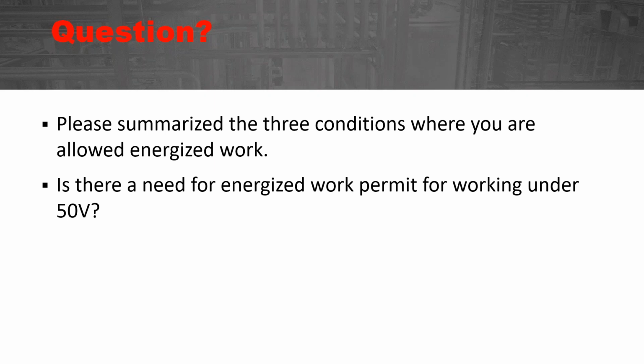Also, I think we've got a question coming up later about continuous process, such as steel making or glass making. I was teaching in a plant in Crossville, Tennessee, about an hour and a half from home, halfway between Nashville and Knoxville. They have an area they would consider continuous process, where ceramic tiles are going through a kiln that is hundreds of feet long, and if they just stop that midway, these tiles are going to burn up and it's going to cause a big problem. Now, all of this, the employer is going to have to demonstrate that working on this energized is permitted. And going back to 70E, if you're going to do work on energized circuits, unless it's less than 50 volts, then you're going to have to fill out and use an energized electrical work permit.